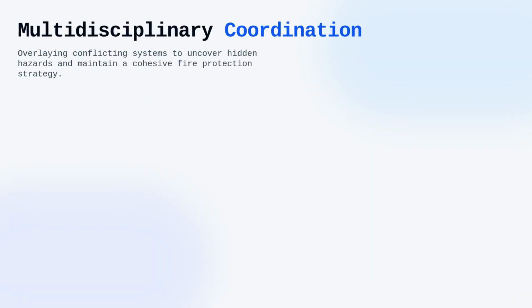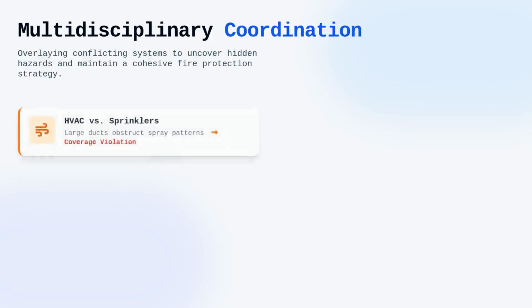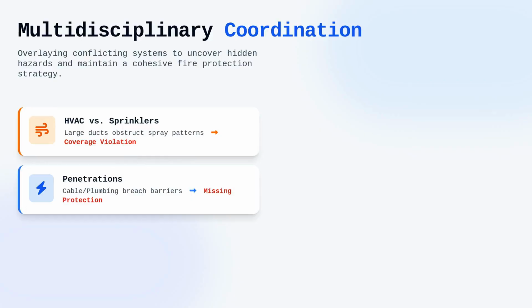Multidisciplinary coordination is perhaps the most challenging aspect of this review because it requires the engineer to overlay conflicting systems to find hidden hazards. A common scenario is the installation of large HVAC supply ducts that obstruct the discharge pattern of a ceiling-mounted sprinkler head, violating the spray coverage requirements. We must also scan for fire-rated barriers that have been breached by electrical cable trays or plumbing runs without the appropriate listed through penetration protection.